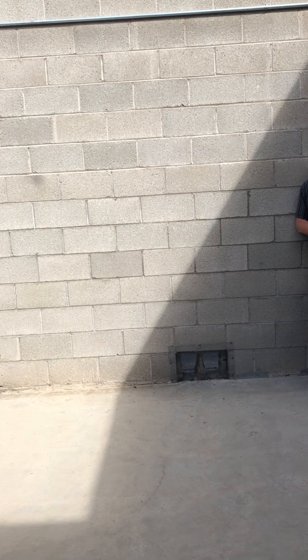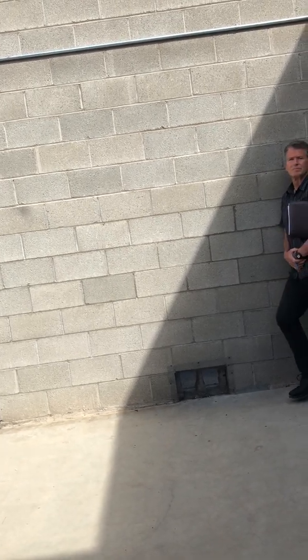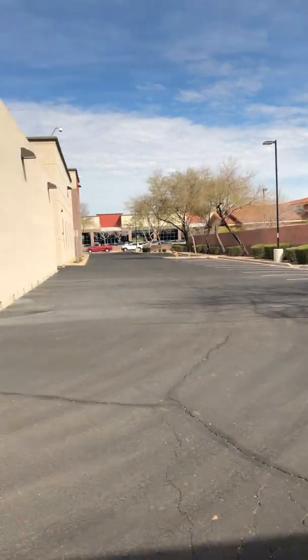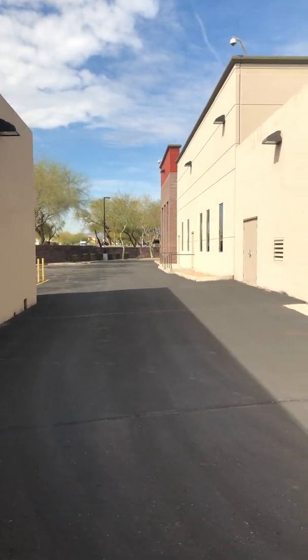We would want to do commissioning for the major gear as you would do at any data center, but it's the wrong time of year to load bank it because the weather's so mild. I've got past load bank reports in my desk, we've got history for the site back to 2015, and we load banked every year until we were cut off, and we did the infrared scans every year, and we fixed everything as we were scanning. Very rarely did we find anything.